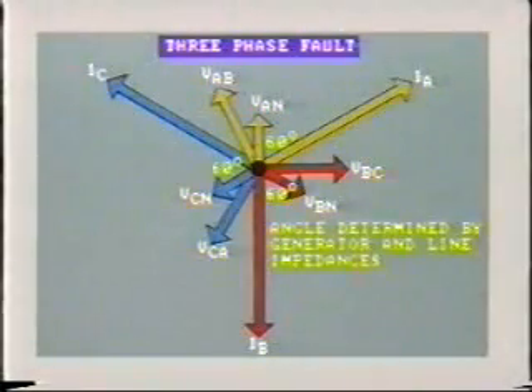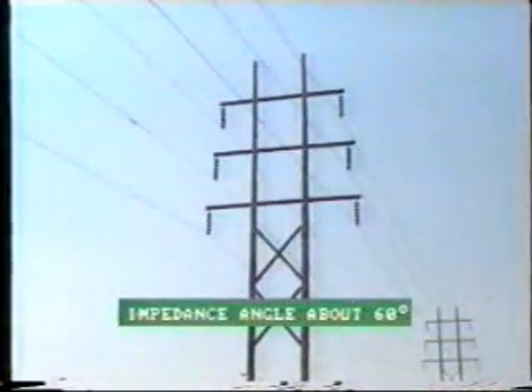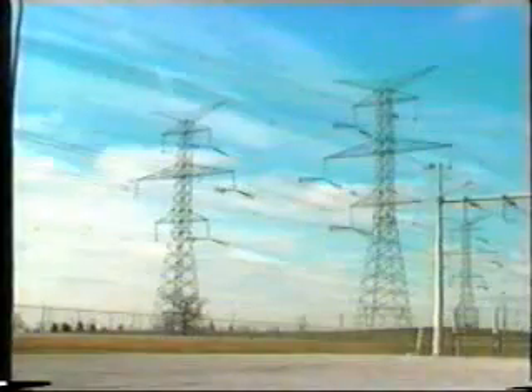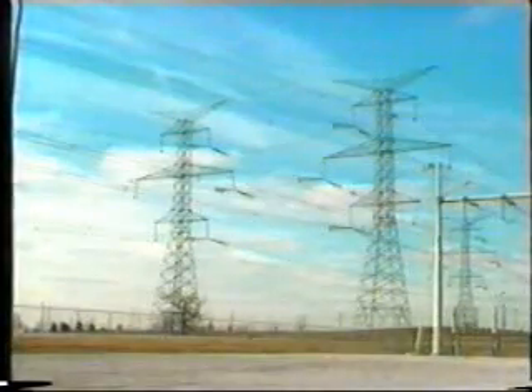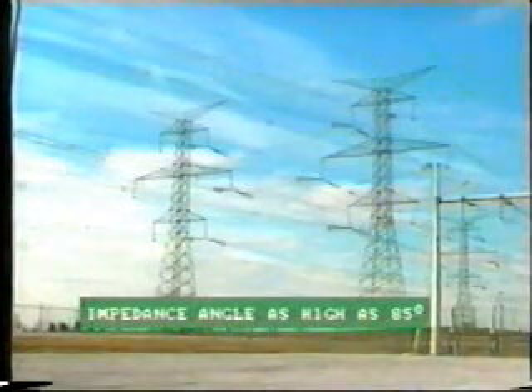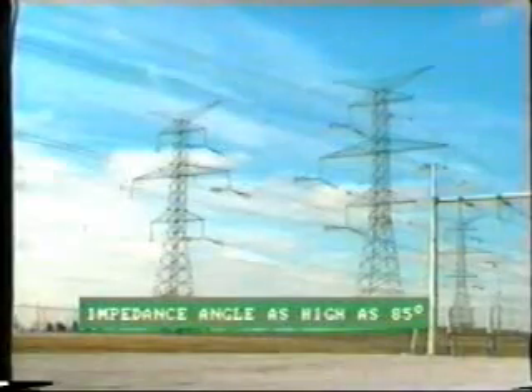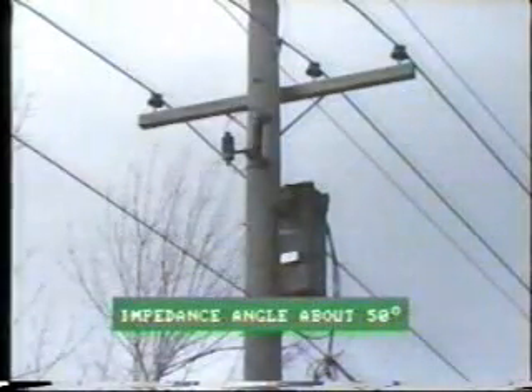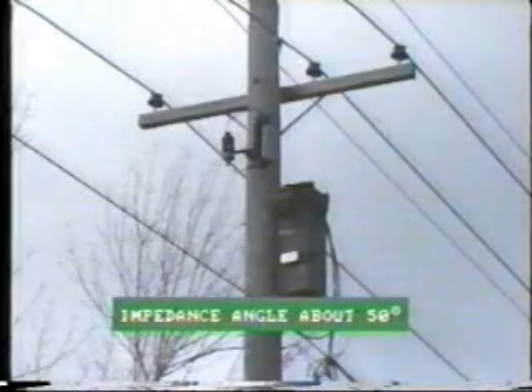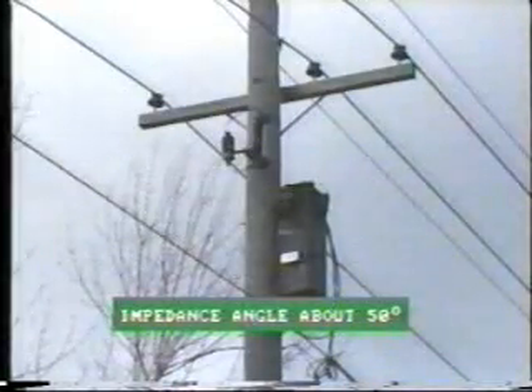Why is this? Well, this angle is determined by the nature of the system impedance to the fault. That is, the generator impedance and the line impedance. The line impedance predominates, and for a 115 kV transmission line, this is usually about 60 degrees. High voltage lines, 230 kV and up, may have impedance angles as high as 85 degrees. Conversely, low voltage distribution lines usually have a line impedance angle of about 50 degrees.